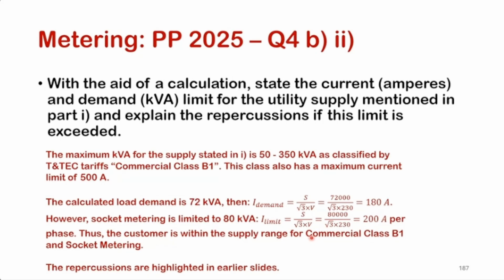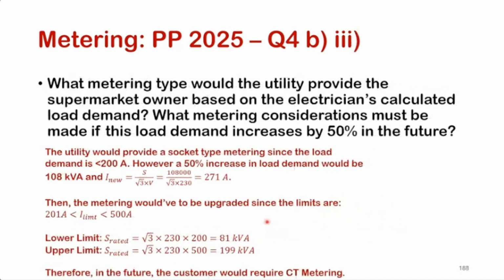Alright, so assuming you are all clear and have no questions. Now they ask what meter and type the utility will provide the supermarket owner based on the electrician's calculated load demand, and what meter consideration must be made if the load demand increases by 50% in the future. So basically answer the question from before. The utility will supply a socket type meter since the load demand is less than 200 amps.